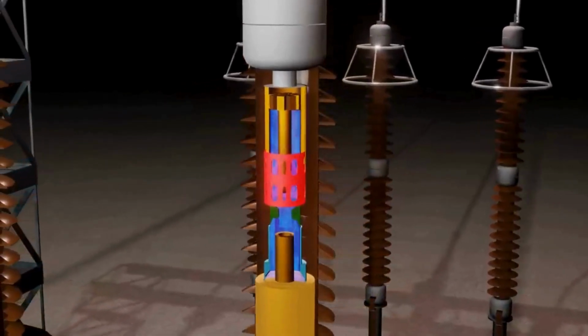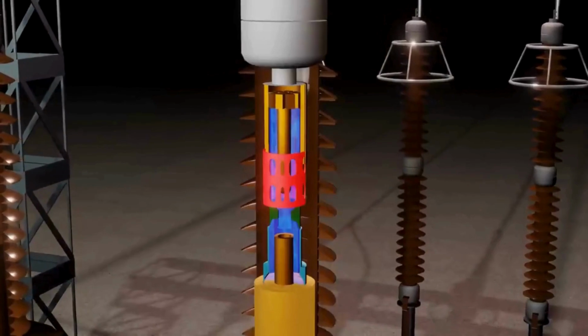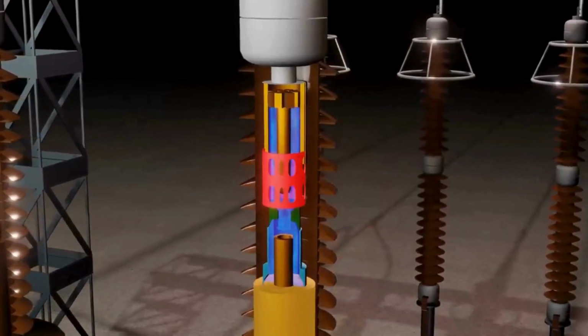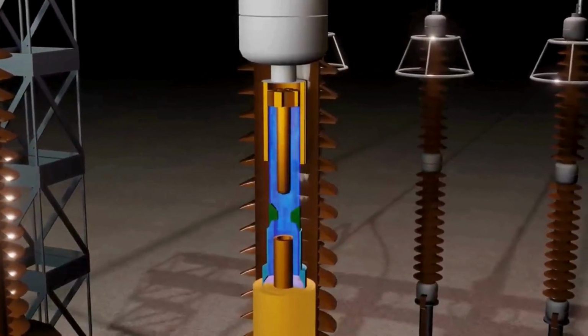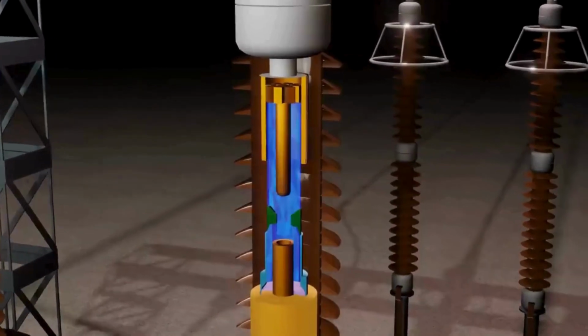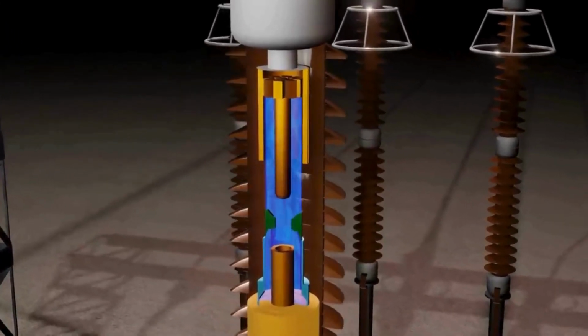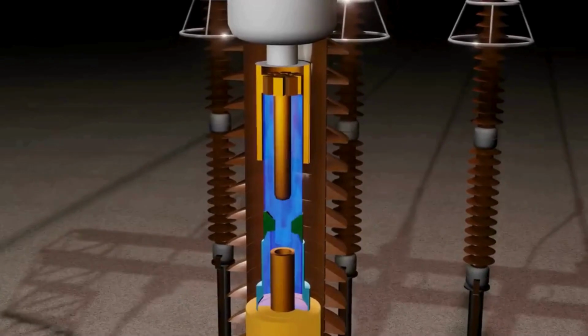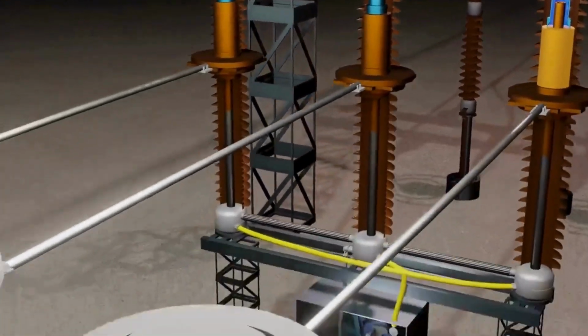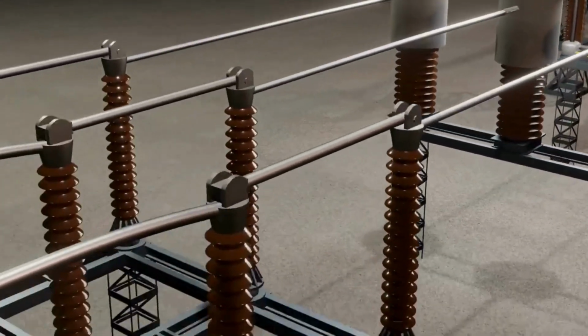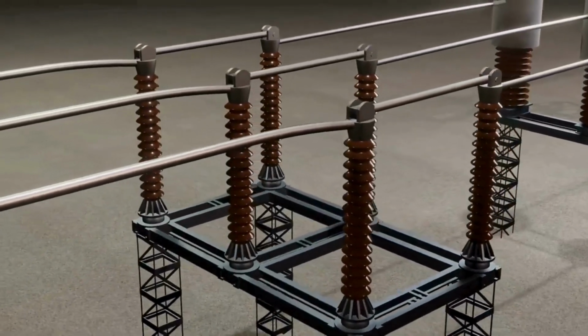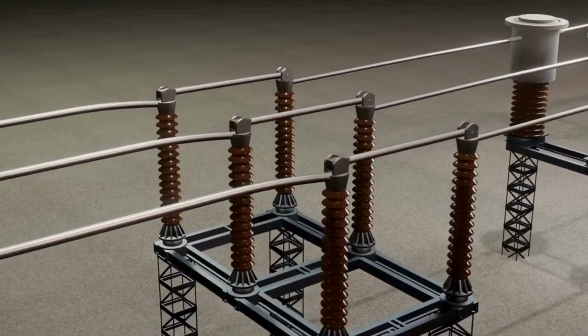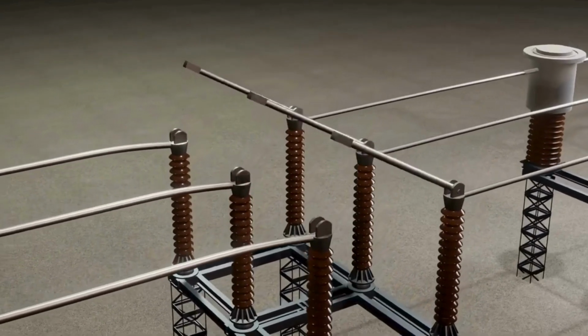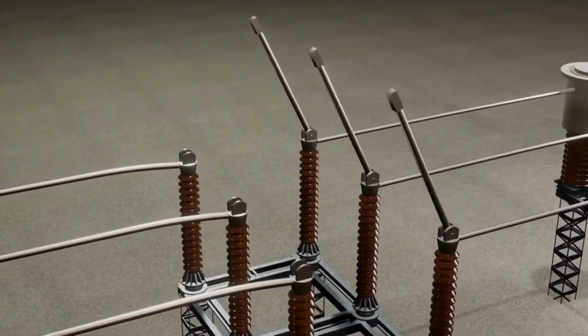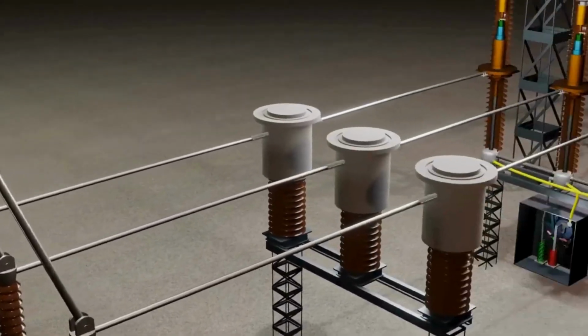For now, the circuit breaker is open, but there is still a risk because the distance between the contacts of these circuit breakers is very small. That's why the isolator is installed after the circuit breaker, so when we manually turn off the circuit breaker to work on a line, then after turning it off, the isolator is definitely opened for double safety. Because when such a powerful line suddenly breaks, there is a lot of stress, and the contact of the circuit breaker is under great stress.